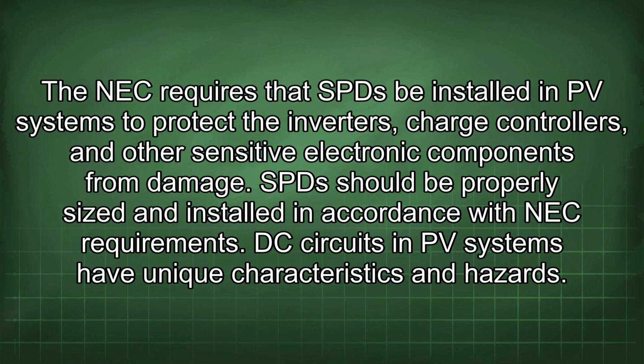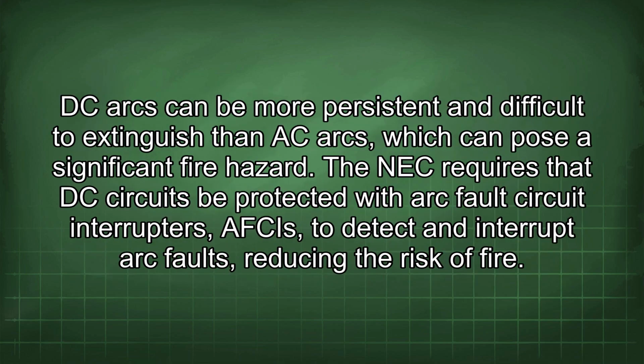DC circuits in PV systems have unique characteristics and hazards. DC arcs can be more persistent and difficult to extinguish than AC arcs, which can pose a significant fire hazard. The NEC requires that DC circuits be protected with arc fault circuit interrupters designed to detect and interrupt arc faults, reducing the risk of fire.